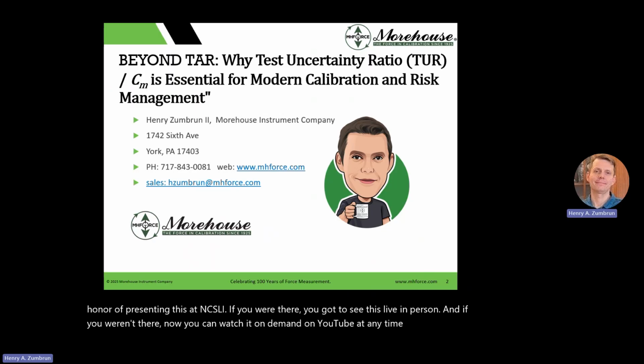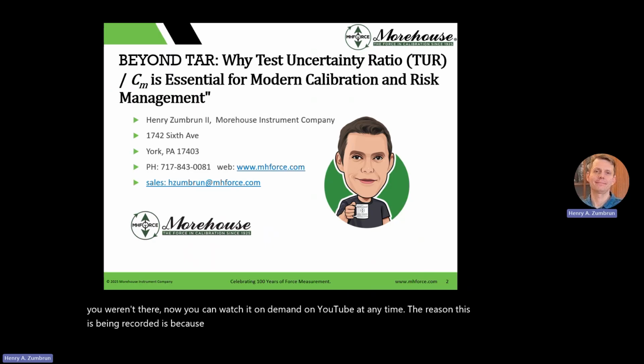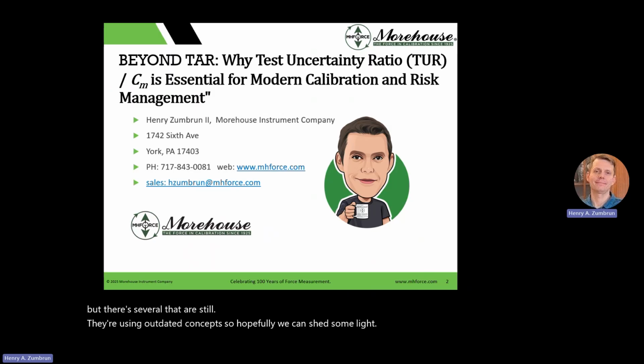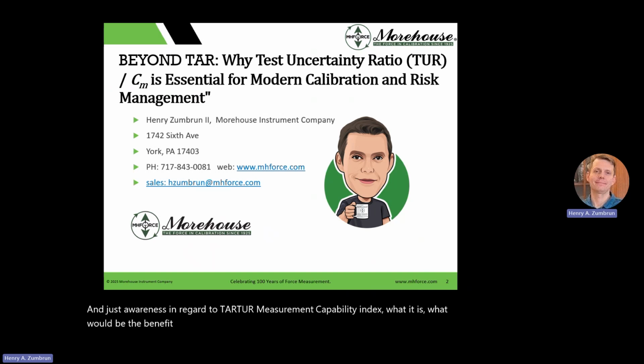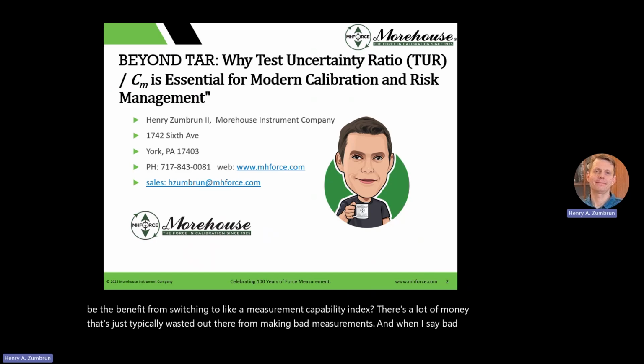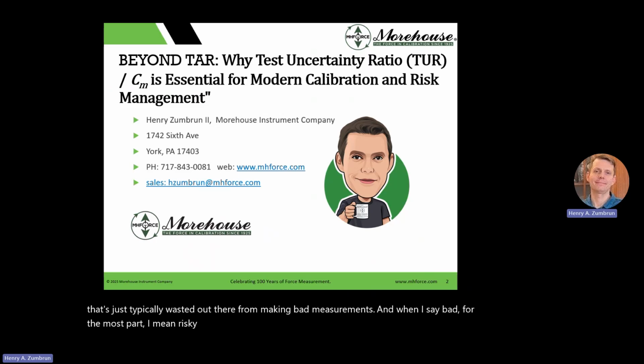The reason this is being recorded is because what was uncovered here is that most calibration labs, not all, but several, are still out there using outdated concepts. So hopefully we can shed some light and awareness in regard to TAR, TUR, and Measurement Capability Index, what it is, and what would be the benefit from switching to a Measurement Capability Index. There's a lot of money that's typically wasted out there from making bad measurements. And when I say bad, for the most part, I mean risky measurements. And we'll help uncover that as we go along.